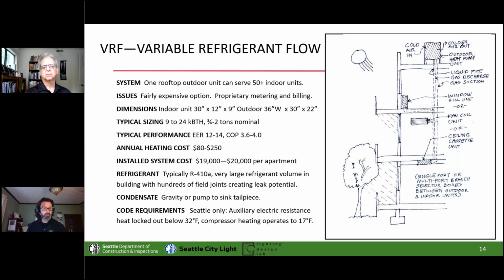Oh, you got to note the refrigerant here. So for the engineers in the crowd, ASHRAE 15 and R410A, there are some really specific rules about the volume of refrigerant you put into a specific volume of room, and a maximum you can reach. And that's something to be thinking about pretty hard here. R410A displaces air. It just is how it is. So it can limit your system volume before you need to start figuring out how to have sensors and controls and some fancier things. And it's something that I don't know that all designers are really taking a hard look at.